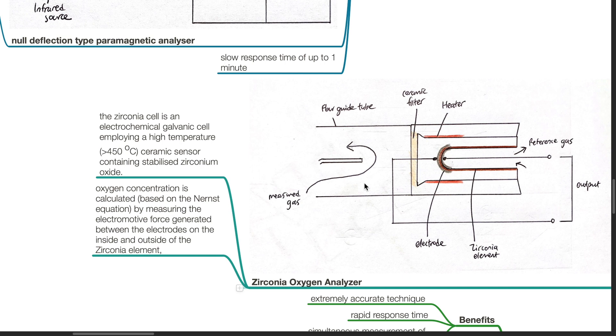The zirconia oxygen analyzer: the zirconia cell is an electrochemical galvanic cell employing a high temperature of more than 450 degrees Celsius, using a ceramic sensor containing stabilized zirconium oxide. Oxygen concentration is calculated based on the Nernst equation by measuring the electromotive force generated between the electrodes on the inside and outside of the zirconia element.